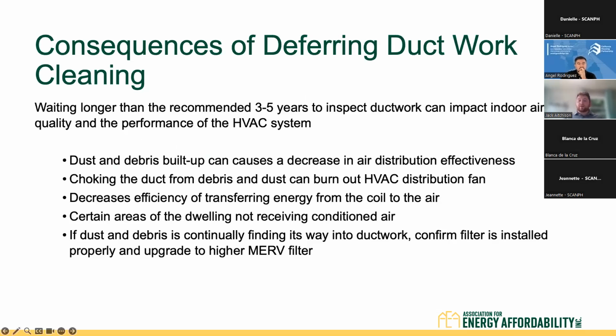So consequences of deferring ductwork cleaning. Waiting longer than the recommended 3 to 5 years to inspect ductwork can impact indoor air quality and the performance of the HVAC system. So dust and debris buildup can cause a decrease in air distribution effectiveness. Going into units all the time, I'm hearing, well, my bedroom doesn't get air, but my living room does. That's typically an issue with the ductwork, and that's going to result in people turning up their set points really high on their furnace, on their heat pump HVAC, whichever, or turn it really cold, trying to condition a space that the duct is clogged and conditioned air can't get to.